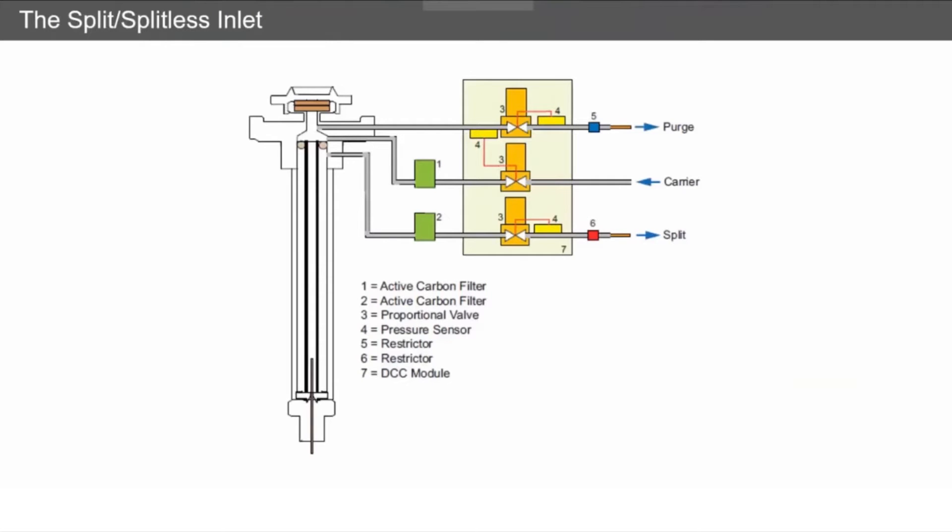How does the split/splitless inlet work? Irrespective of manufacturer, this is essentially what a split/splitless inlet will look like. You have a purge flow coming out the top to take away any septum bleed and keep the top of your liner clean. You've got your carrier gas going in - the flow is controlled by pressure restrictors and various sensors. Then you've also got your split line coming out.